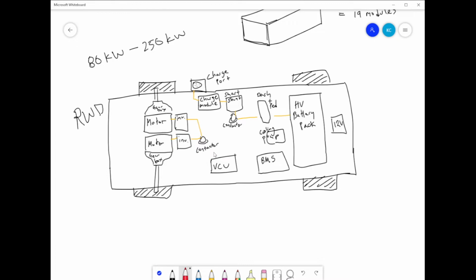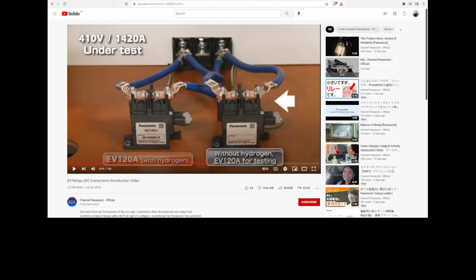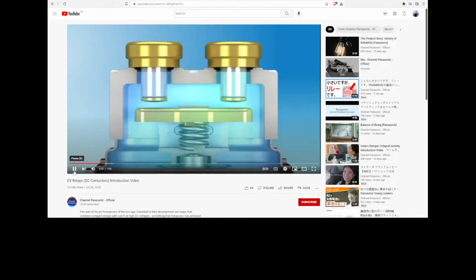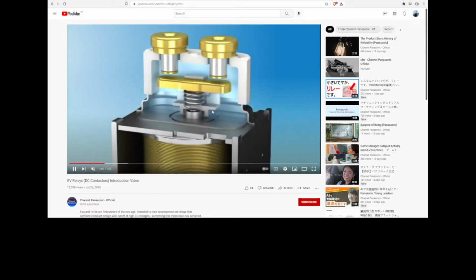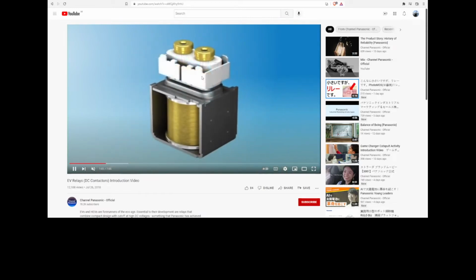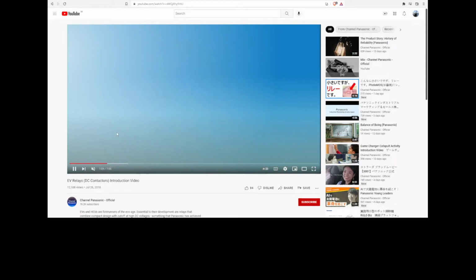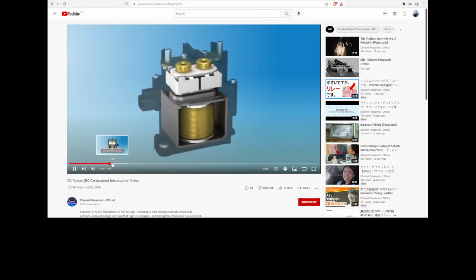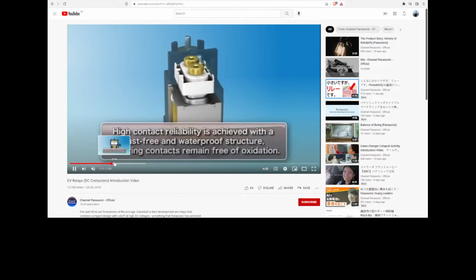Next, we're going to put a contactor on there. I'm going to show you a little more about contactors. Here we see one of those Panasonic contactors under test, and yeah, you'll fry it. That's what it's kind of for. It's just a mechanical connection to protect your circuits. It'll close, and they put hydrogen inside this chamber to reduce the arcs, keep those controlled, because every time you make contact, there's going to be an arc flash.